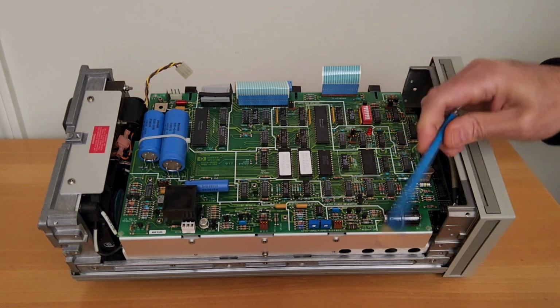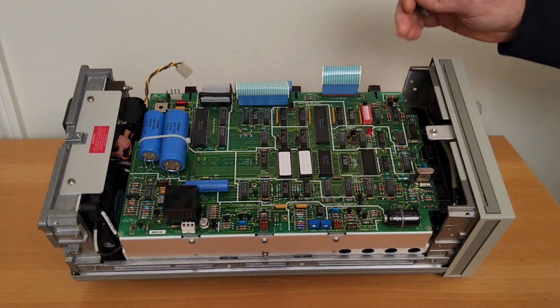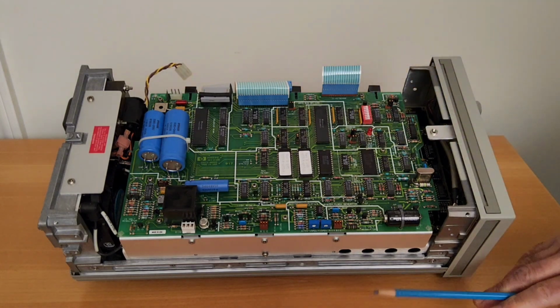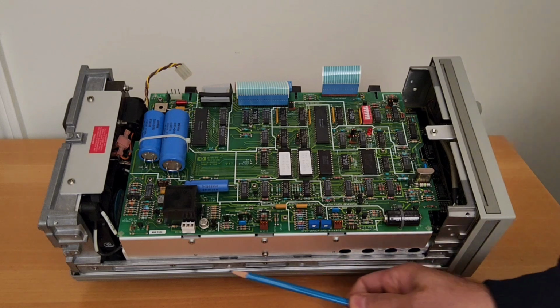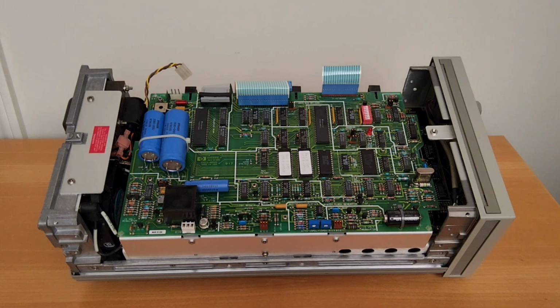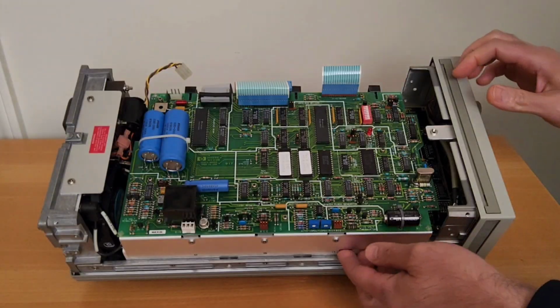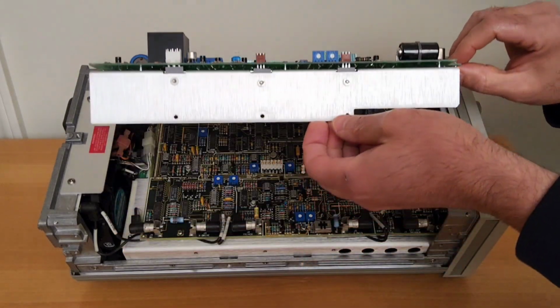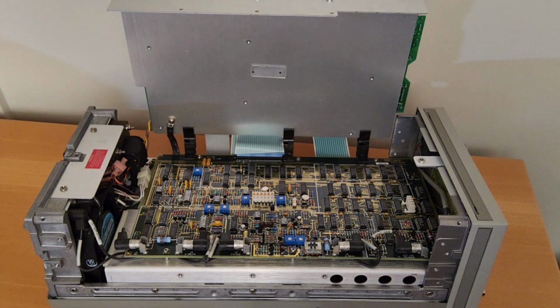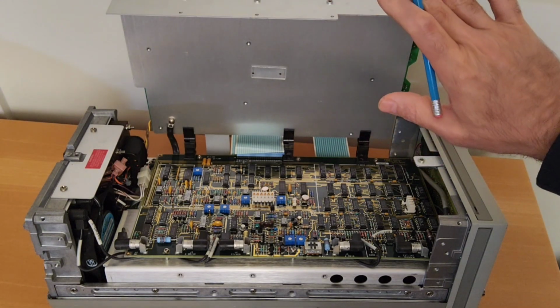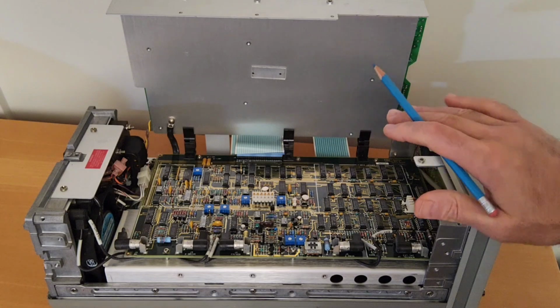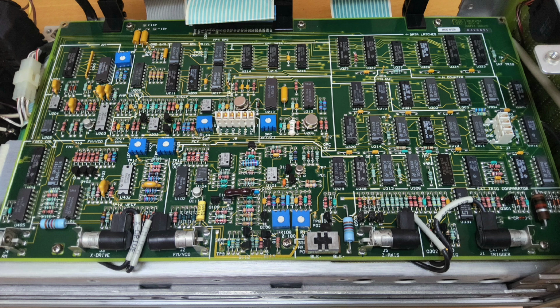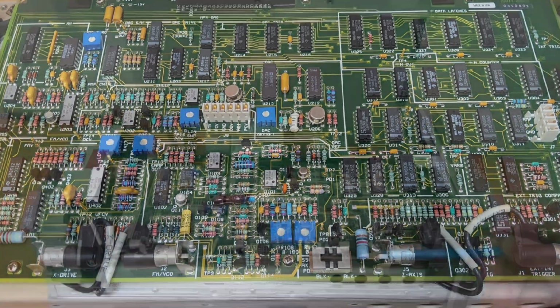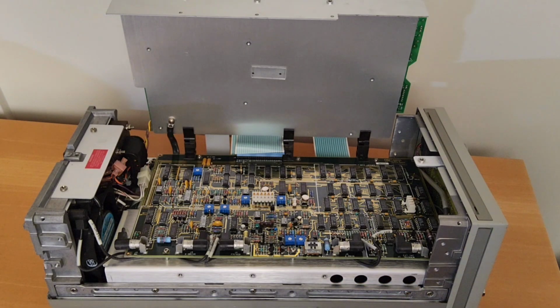This main board tilts up on these 3 hinges on the back. Just need to remove these 3 screws in the bottom, 2 of which I have already removed. So we'll go ahead and remove this last screw so we can rotate the top board up. Okay, so we have now lifted up the CPU controller board. It doesn't go all the way to 90 degrees, so I've tilted the unit slightly to make sure that it stays up. In the service manual, this board that we're looking at is referred to as the mode board. And there are still more boards underneath that we're going to look at.